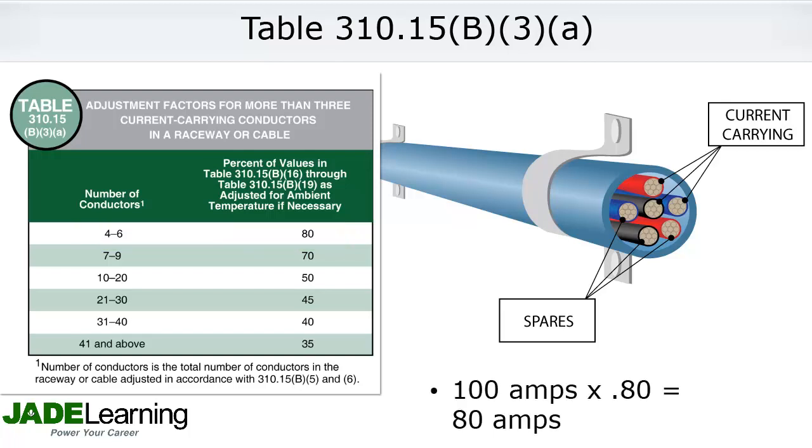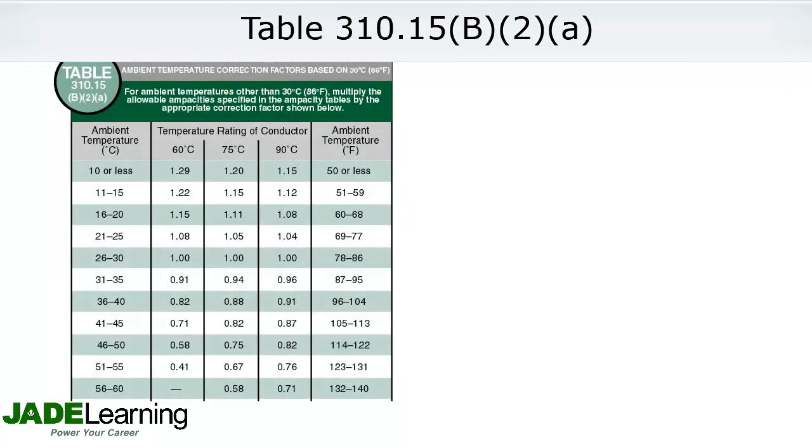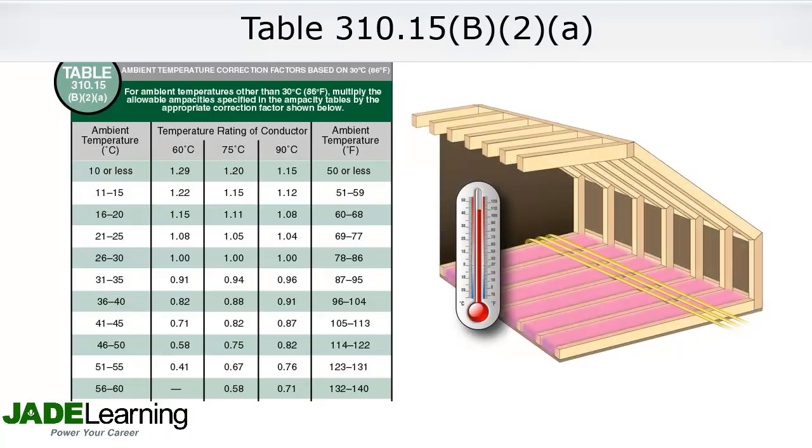When the ambient temperature is hotter than 86 degrees Fahrenheit, table 310.15(B)(2)(A) must be used to calculate how much current the conductor can carry. If the temperature in an attic is 110 degrees Fahrenheit, a type NM cable cannot carry its full rated load.